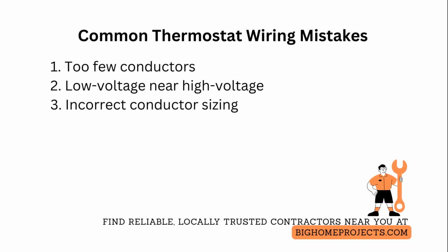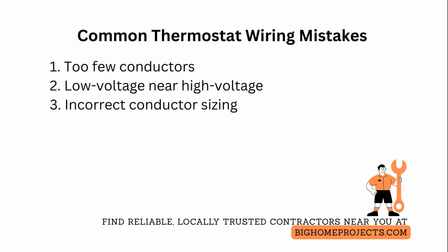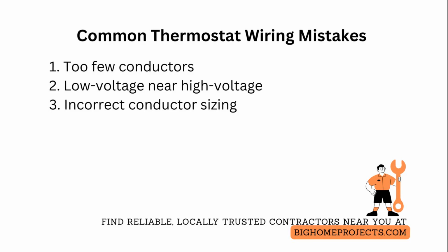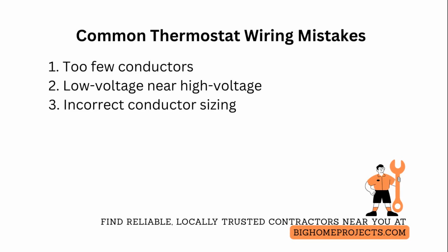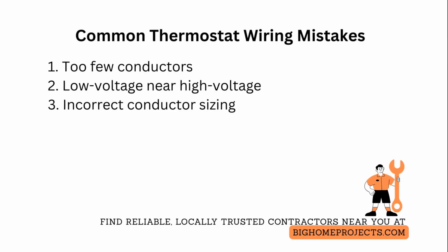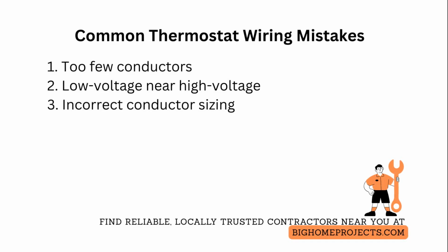The third frequent problem is incorrect conductor sizing and long runs causing voltage drop and unreliable operation. Correct this by choosing 18 gauge for typical homes, upgrading to 16 gauge for very long runs, and measuring actual resistance with a multimeter during installation.